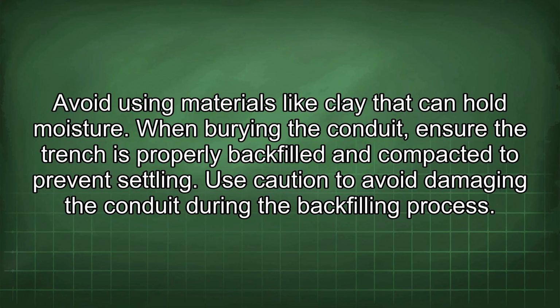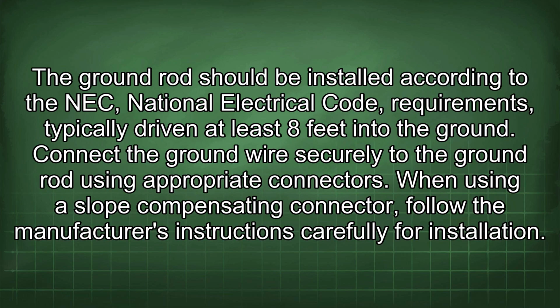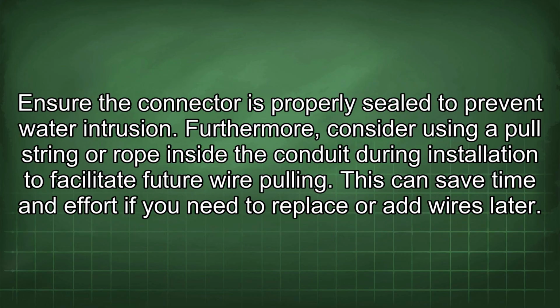When burying the conduit, ensure the trench is properly backfilled and compacted to prevent settling. Use caution to avoid damaging the conduit during the backfilling process. The ground rod should be installed according to the NEC National Electrical Code requirements, typically driven at least 8 feet into the ground. Connect the ground wire securely to the ground rod using appropriate connectors. When using a slope compensating connector, follow the manufacturer's instructions carefully for installation. Ensure the connector is properly sealed to prevent water intrusion.